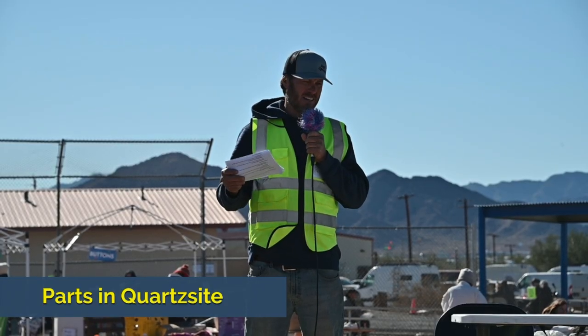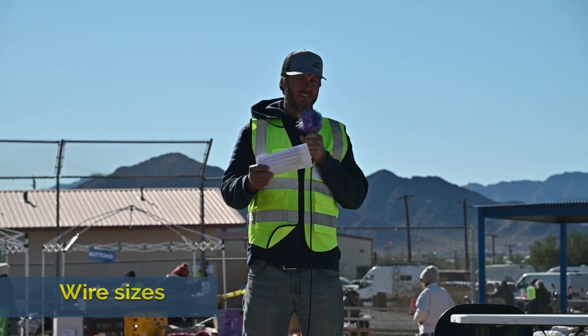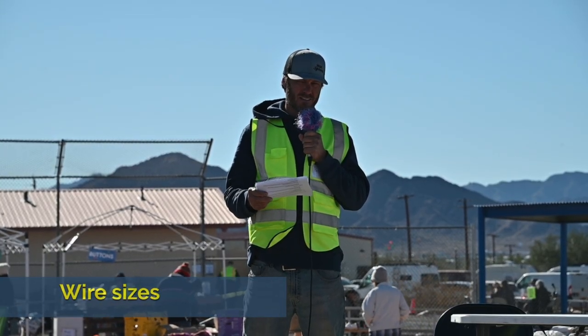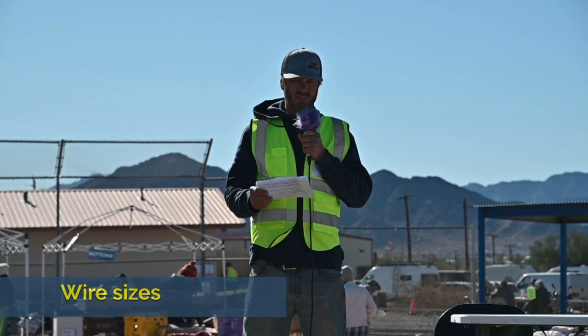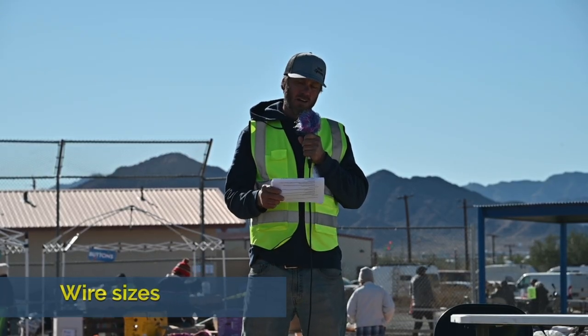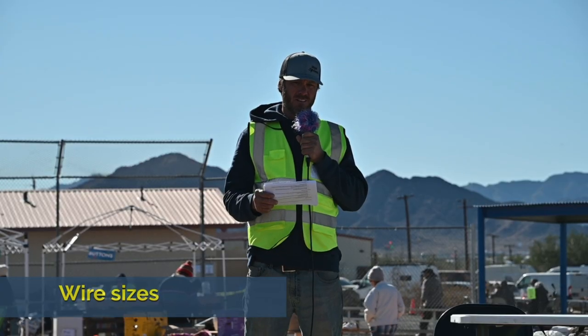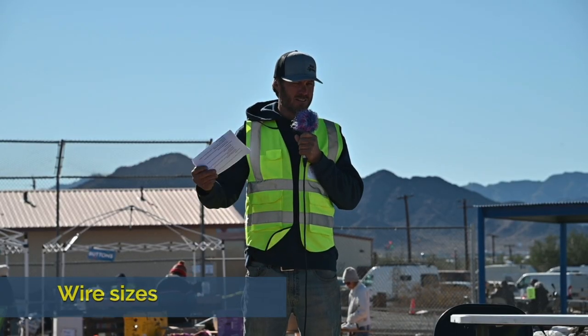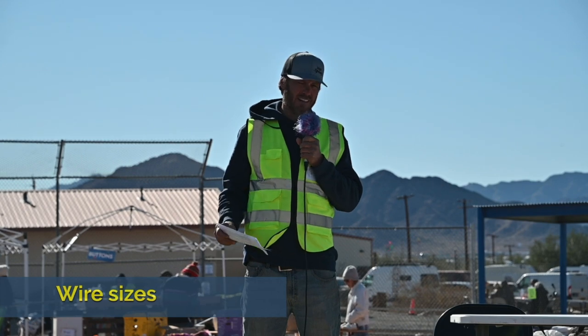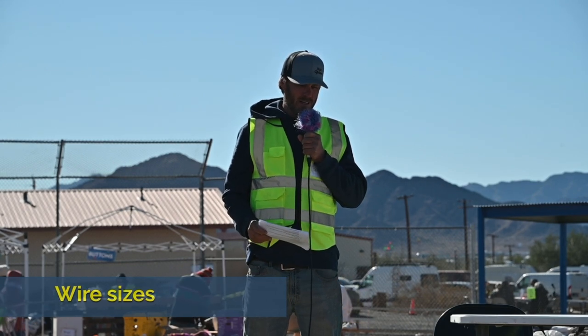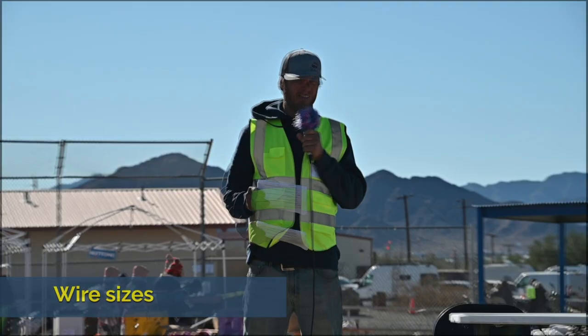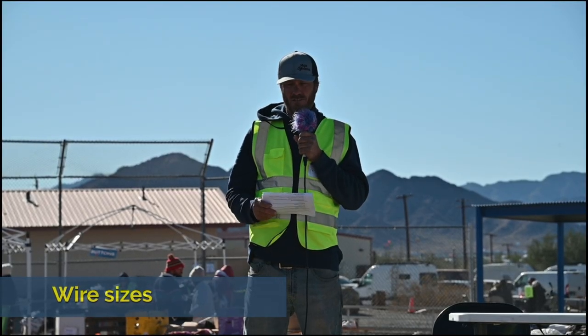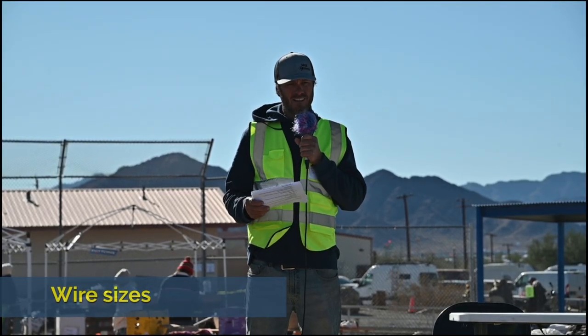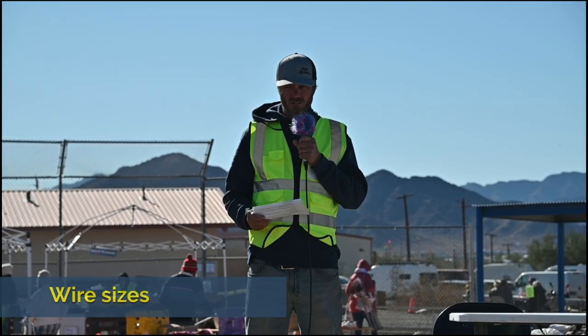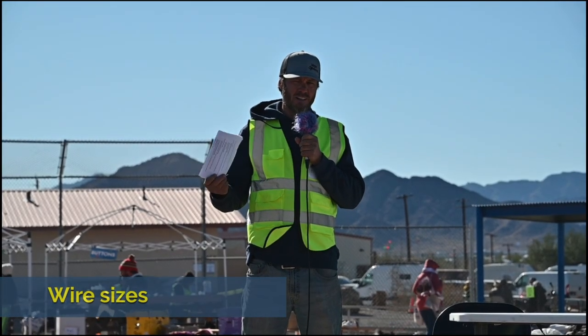Again, back to the wire sizes. I see a lot of systems with undersized wires or no fuses. Undersized wire is expensive. Copper is expensive, I know it. A T-fuse for my system cost me about $180. I understand that. That's cheaper than me having to buy a new bus if it burns down. And I'm going to say that out loud. It's the truth. A lot of times these small wires are either going to melt, or it's going to stink. Hopefully you smell it before anything else happens.